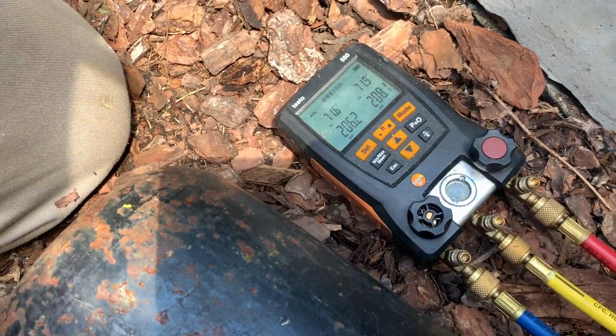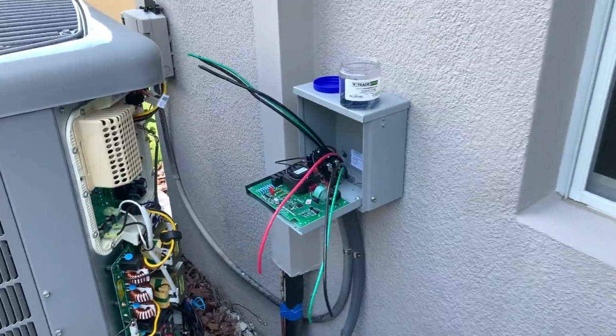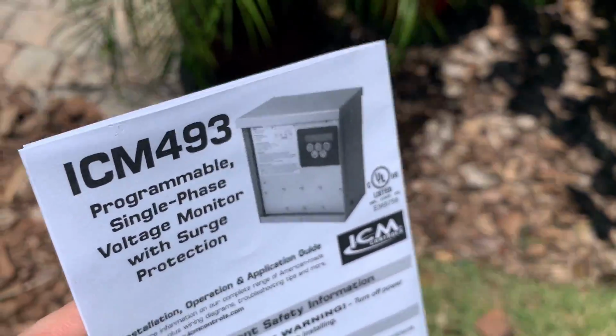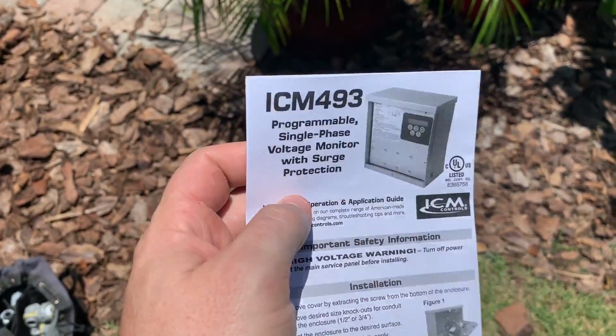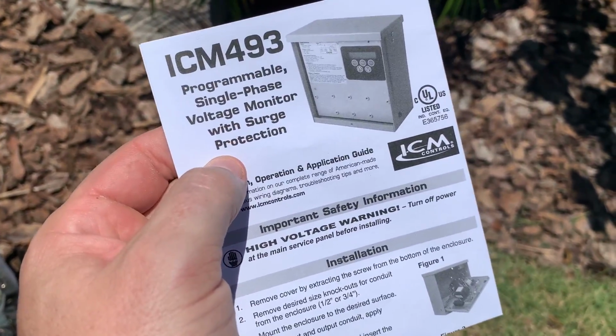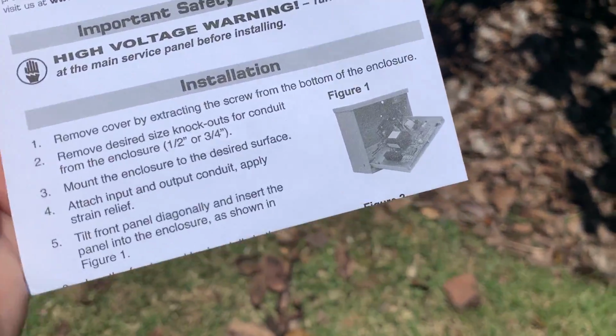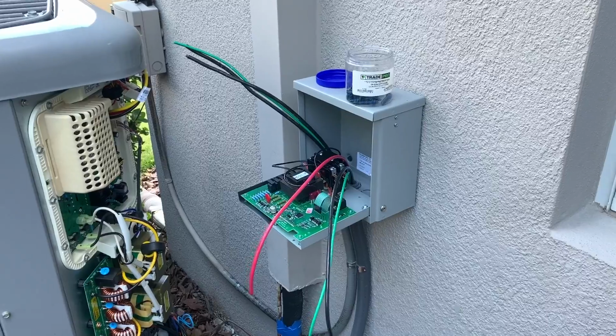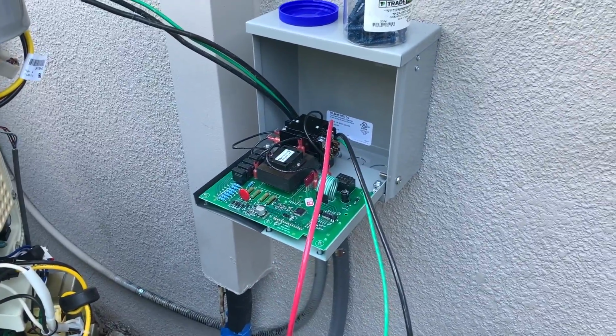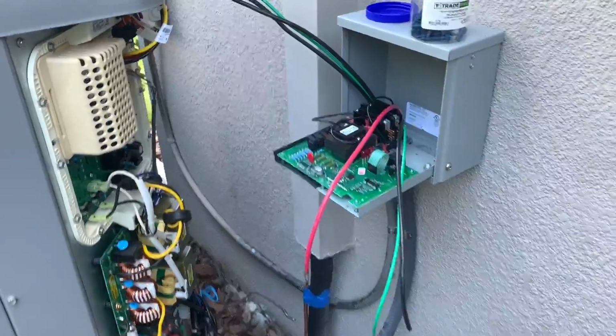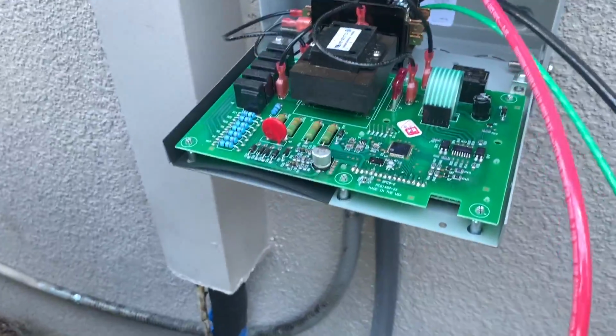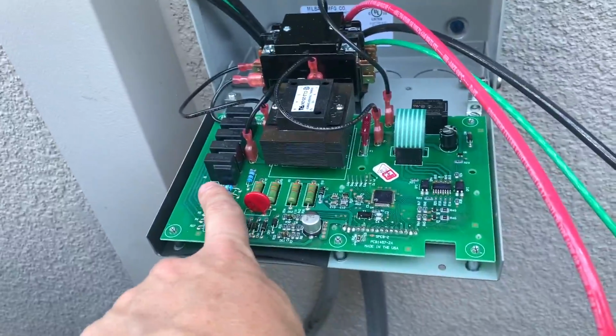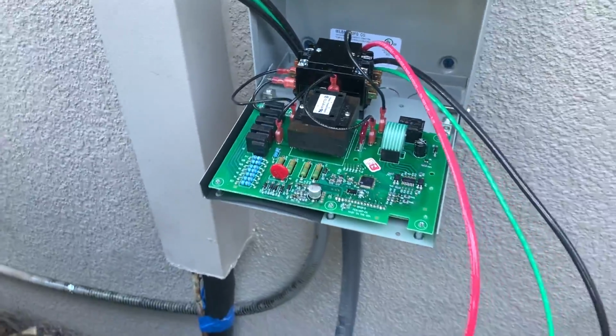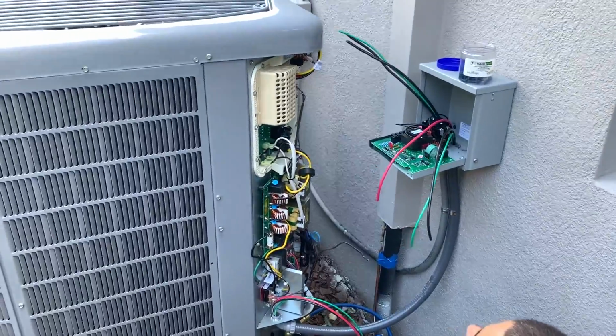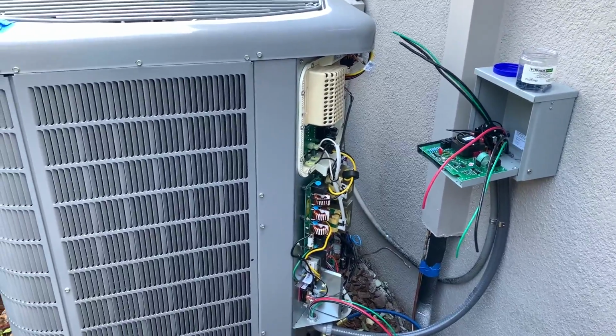Under pressure test right now, holding nice. We're using the ICM 493 in and out because this is still an inverter driven piece of equipment. We always want to be careful to make sure that we're not giving it continuous over voltage or power surges, which is what the ICM 493 does well. Both a phase monitor, voltage monitor, and a surge protector. 5 metal oxide varistors in parallel. So we got 1, 2, 3, 4, 5 metal oxide varistors that helps protect it. Because again, you don't want to spend all that money on this bad boy and have it go out.